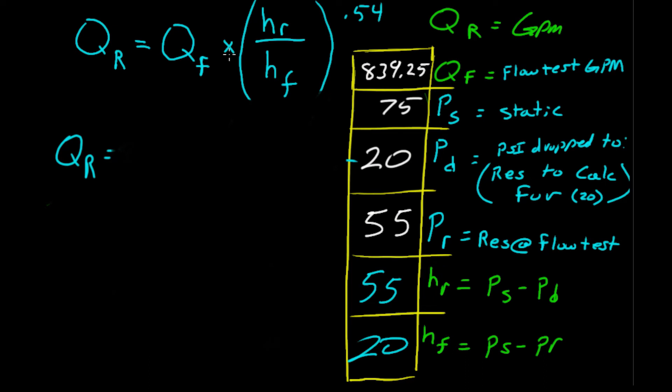QR equals QF times H sub R over H sub F. And you can say Q sub F, Q sub R. That's actually the proper way. But if you say QF and QR, we'll know what you're talking about. So, our QF in our original equation, non-simplified, or actually this is a simplified equation, is 839.25 gallons a minute, times our HR is PS minus PD is 55. Now, our HF number, PS minus PR is 20, 0.54.